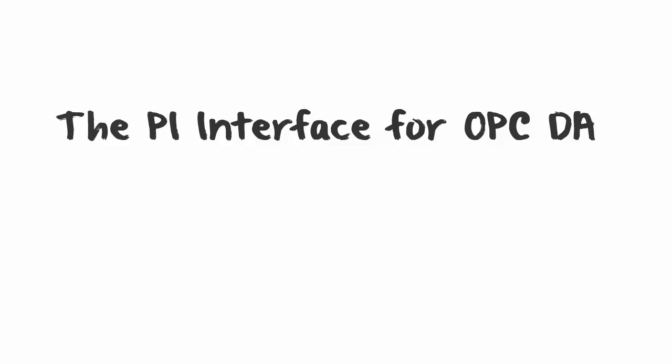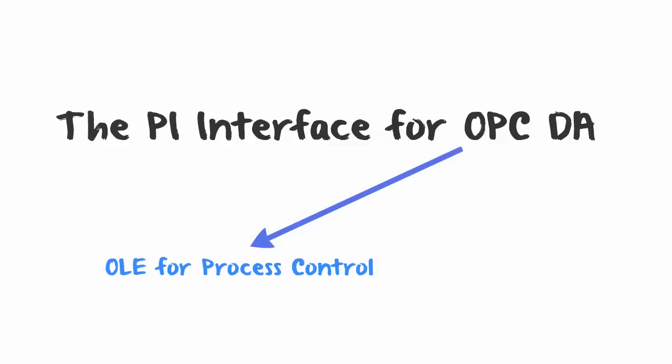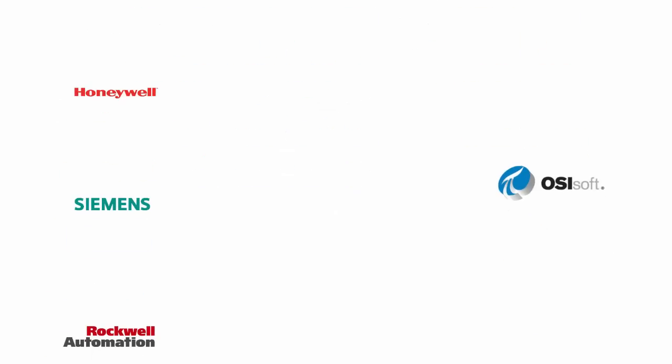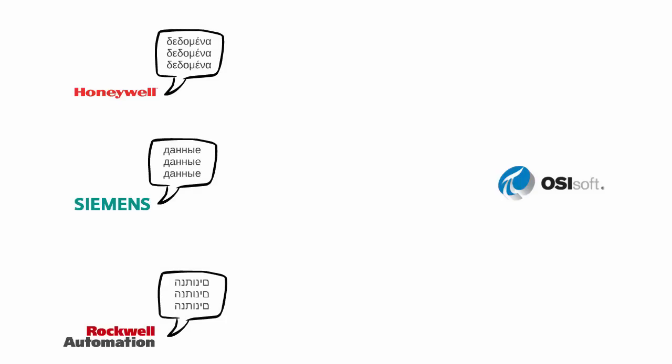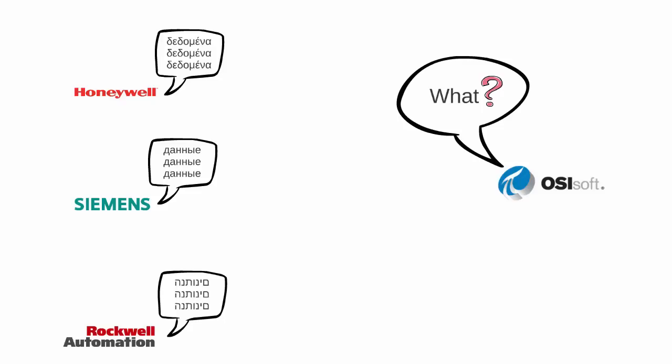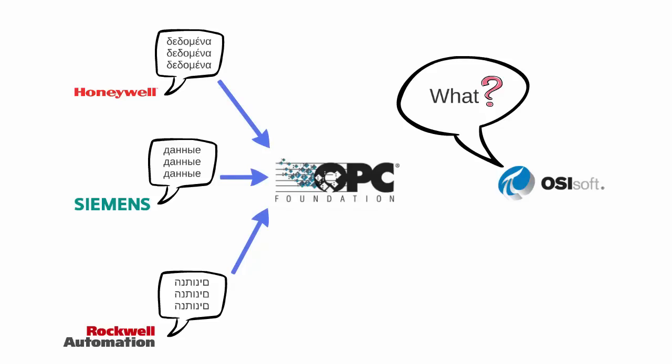The PI Interface for OPC DA is used to collect data from an OPC DA server. In order to understand what an OPC DA server is, we first need to understand what OPC DA means. OPC stands for OLE for Process Control, and DA stands for Data Access. So OPC DA is a standard to communicate data across automation systems. Here we have a bunch of different vendors with different automation systems speaking different languages, and the PI system also speaks its own language, so these languages need to be translated. People in the automation industry came up with the OPC standard as a standard way to expose and collect data on these systems — basically a standard created to facilitate data sharing.